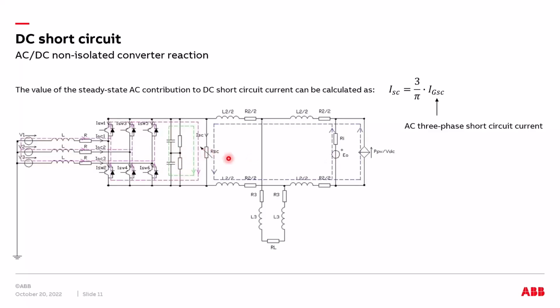Then we have a green dotted line contribution, which is the contribution coming from the DC capacitor discharge current. Usually when we have a DC converter, we can have a huge capacitor on the DC side of tens of millifarads. So we can have a huge DC capacitor discharge current peak of up to 300,000 to 400,000 amps, lasting usually less than 1 millisecond, but it can be very large. And then we can have the AC grid contribution passing through the freewheeling diode, which cannot be limited or interrupted.